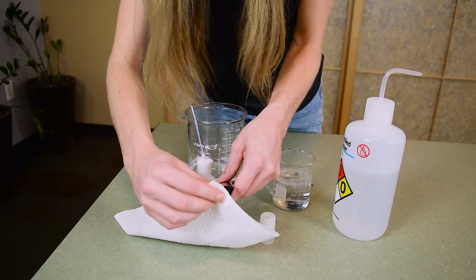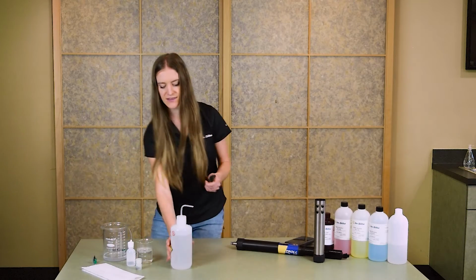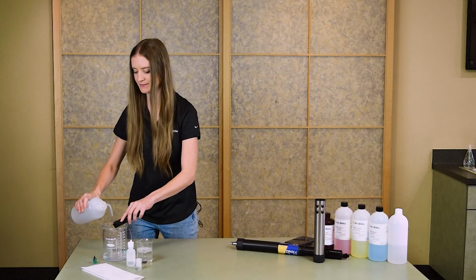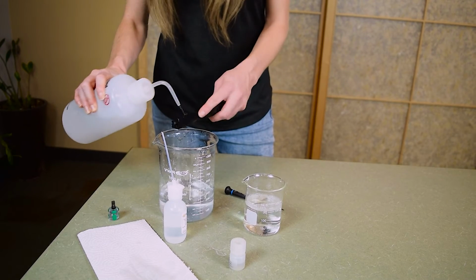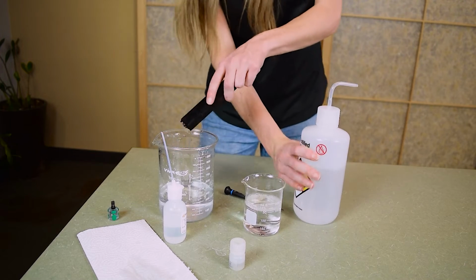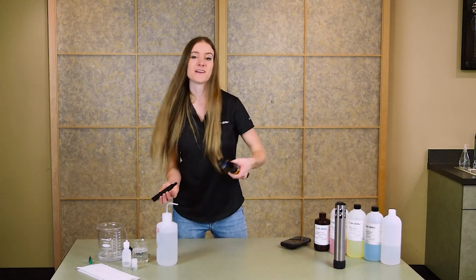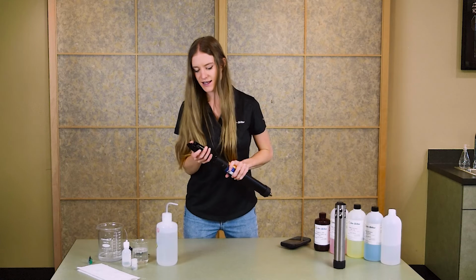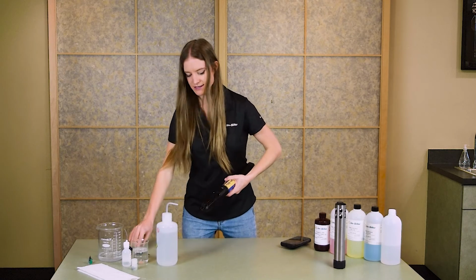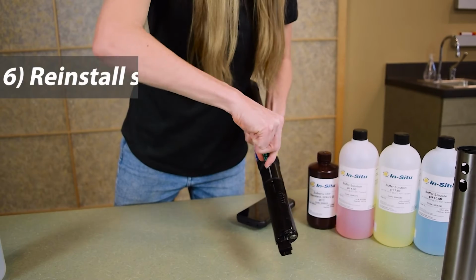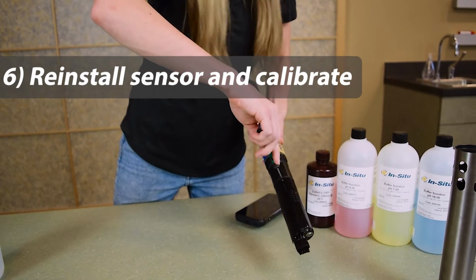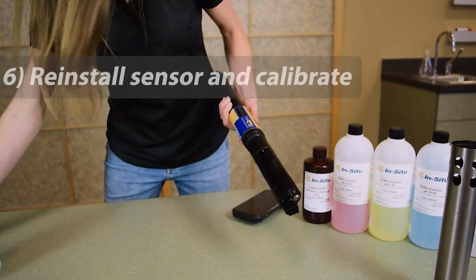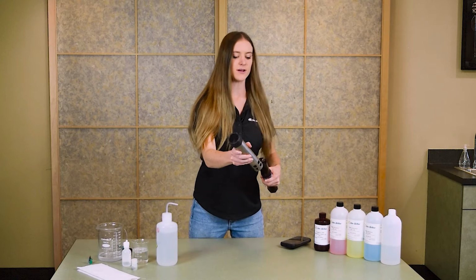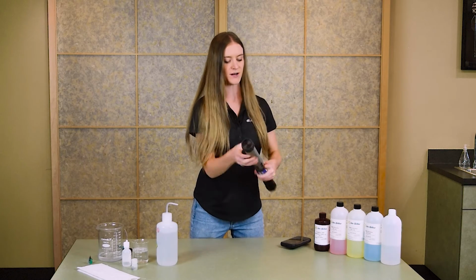Blot any excess filling solution off with a paper towel, and then give the sensor one more rinse with water. Now all that's left is to reinstall the sensor back into the instrument and calibrate it. Slide the sensor into the port and then tighten the sensor set screw. Install the restrictor in calibration mode so that we can use the built-in calibration cup.